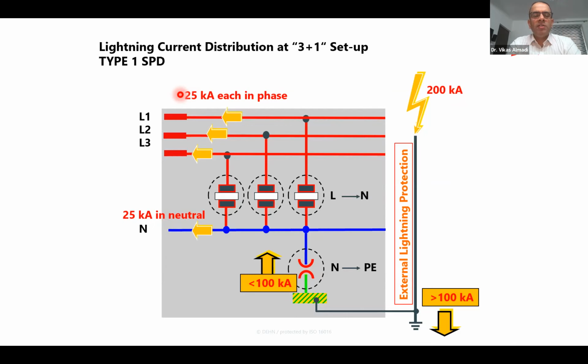We have to use the arresters in 3+1 circuit. Here you see 3+1 circuit. It is visible here. You see, sir, 3 between each line and one common point, right? And 1 between this common point and the earth. So this is 3+1 setup basically. If we use the 4+0 setup, because there are 4 lines only with respect to earth, right? Earth itself is a line in our homes. Then in that case, we will use each arrestor here. First of all, you see here, each arrestor is connected between line and neutral here. And then neutral to earth. Neutral is the central point here, right? In 4+0 system, we will have earth as the central point, where all the arresters will be used from these lines extended to the earth, even neutral to the earth.